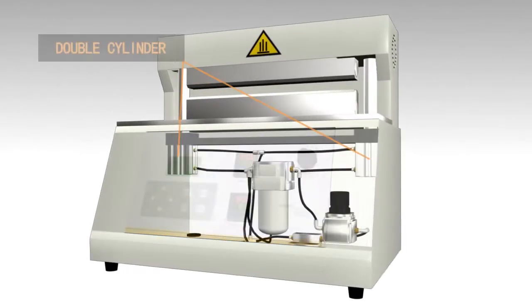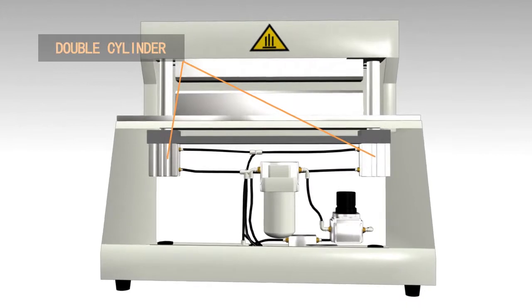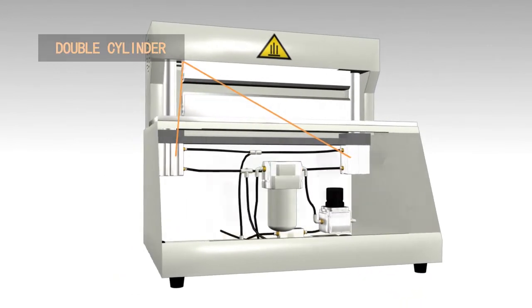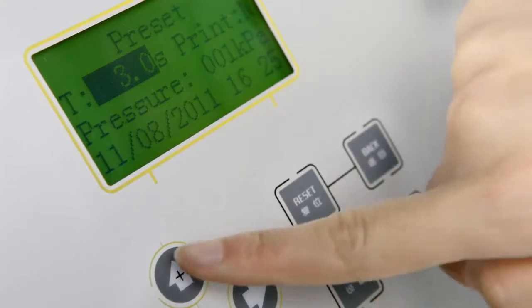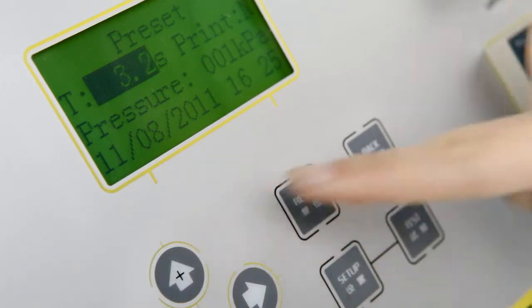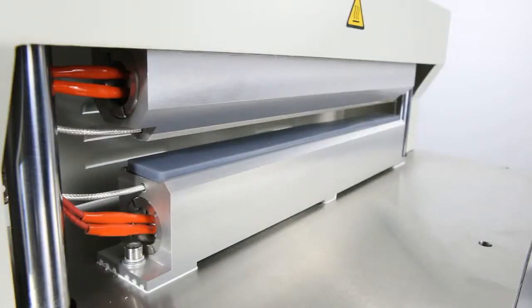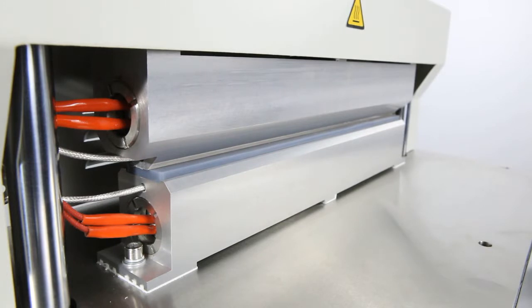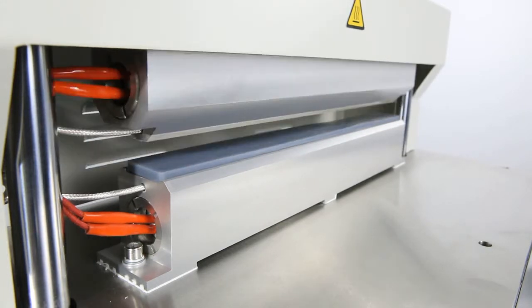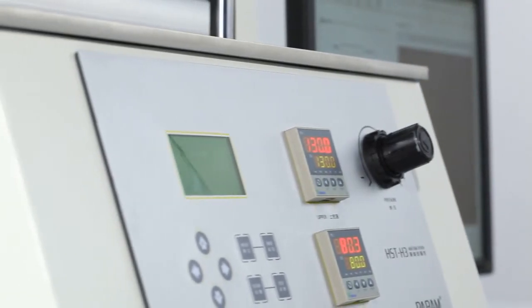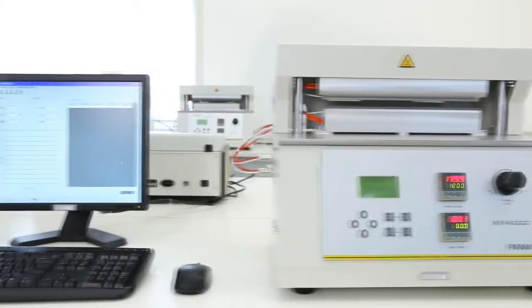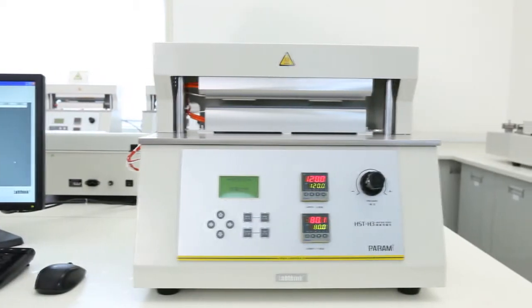Adopting the design of underlying double cylinder closed loop, the pressure control system can perform the function of automatic pressure tuning, which ensures high accuracy pressure control and pressure stability during the testing process. The high resolution counter control of the single chip microcomputer provides a highly accurate dwell time.